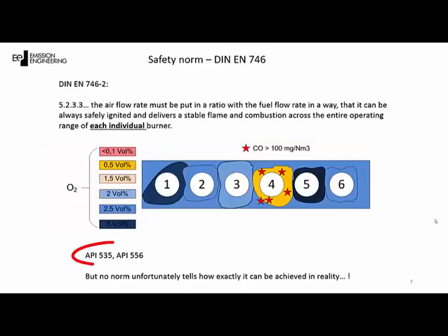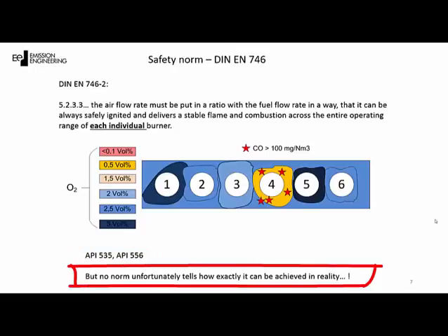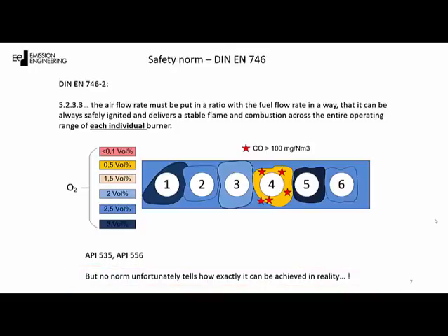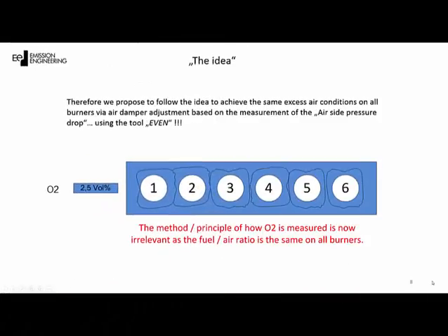There are other norms like API 535 or API 556 that say similar things, but it's curious that none of them tells exactly how the proper fuel-to-air ratio on every burner can be achieved. This is why we came up with a very practical way to approach the problem.